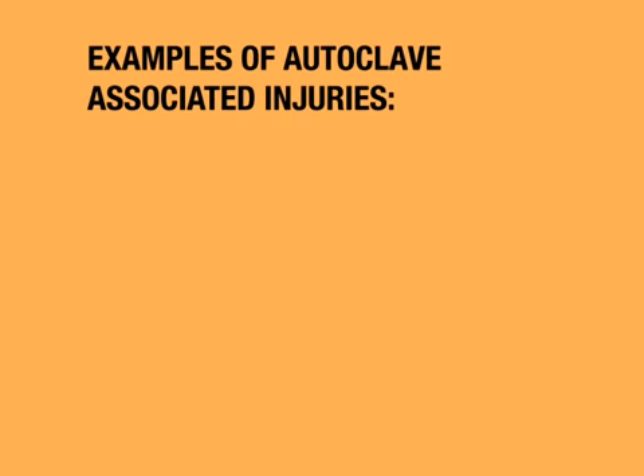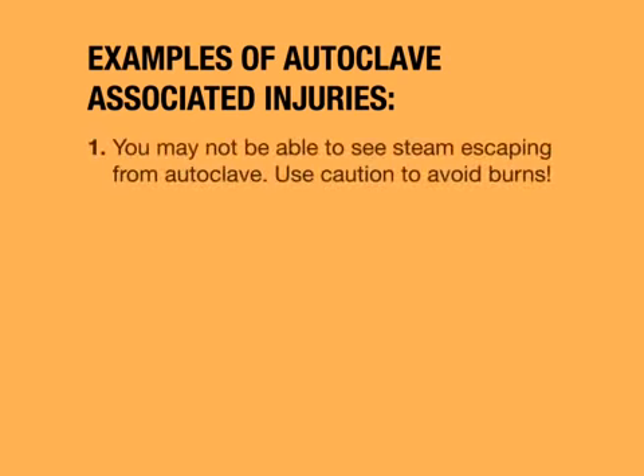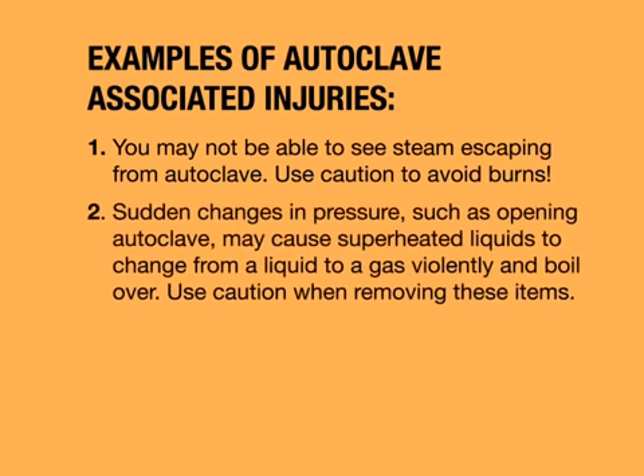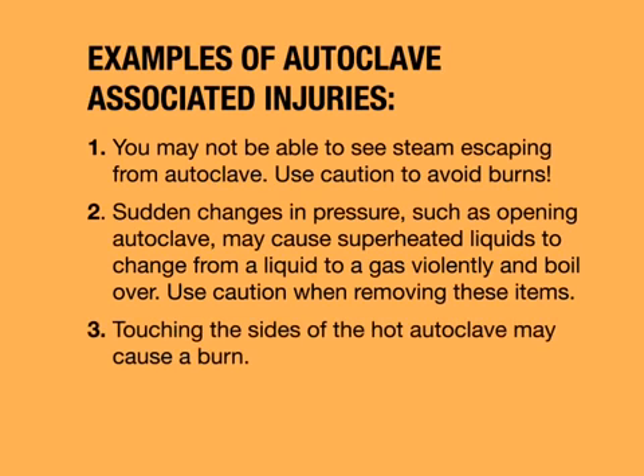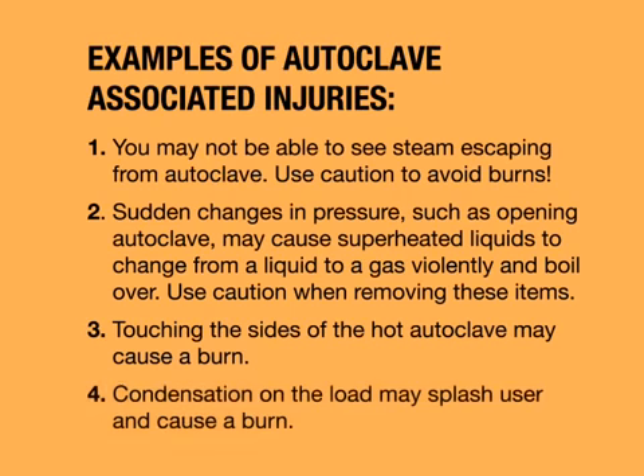Examples of autoclave-associated injuries: you may not be able to see steam escaping from autoclave. Use caution to avoid burns. Sudden changes in pressure, such as opening autoclave, may cause superheated liquids to change from a liquid to a gas violently and boil over. Use caution when removing these items. Touching the sides of the hot autoclave may cause a burn. Condensation on the load may splash user and cause a burn.